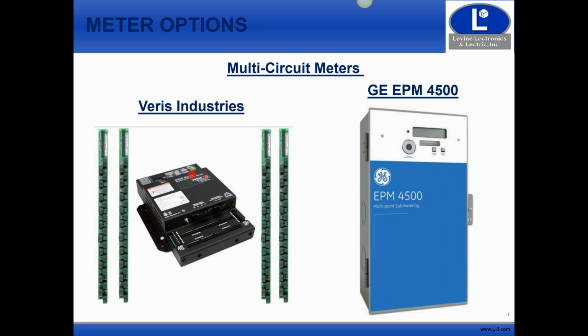Okay, so where this is a possibility, let's say it's an afterthought from a design standpoint, and the engineer has got mixed loads all over the place, and, oh no, now we've got to monitor this, and we forgot it. You can put this in here, and then we can handle the separation at the metering and monitoring level. Now, there is an issue with that in some cases. There's a cost associated with that. So let's think about this. Typically the projects that we've been working on are anywhere from 10 to 30 panel boards or metered boards or metered areas.